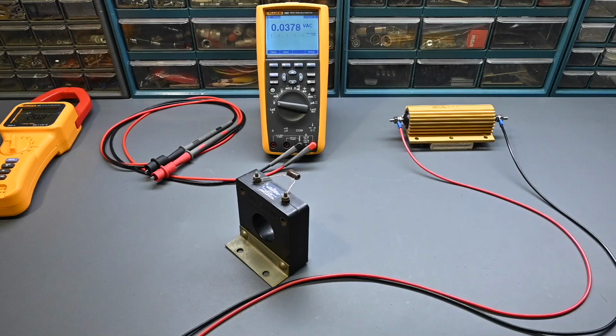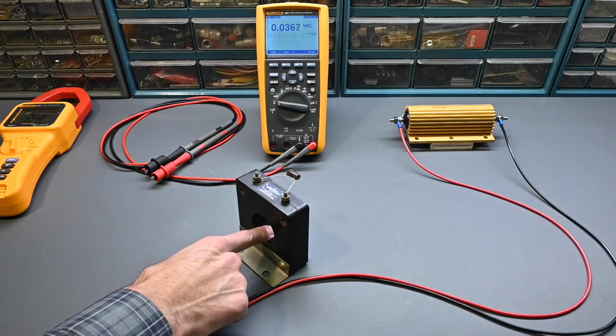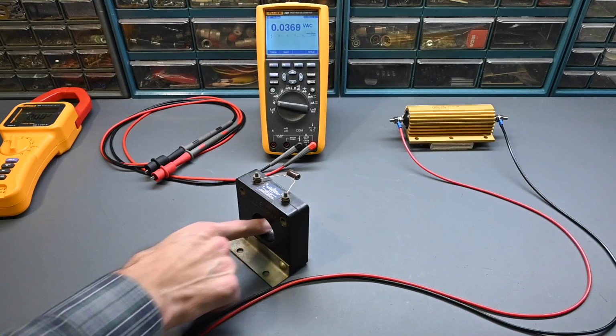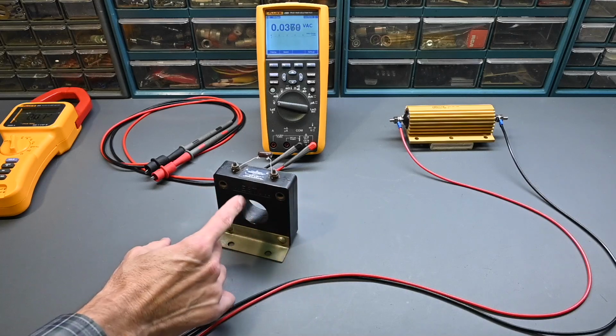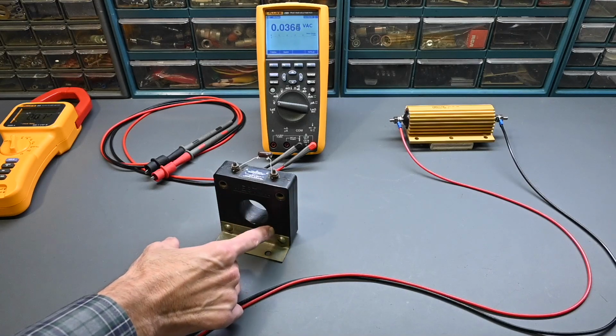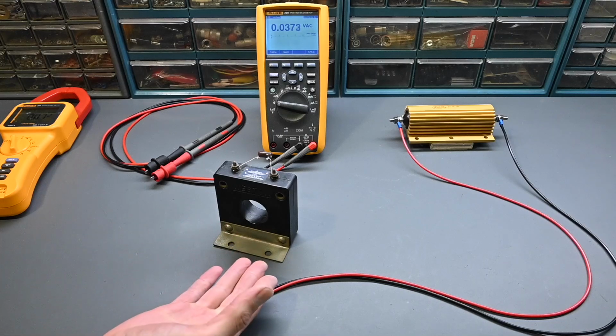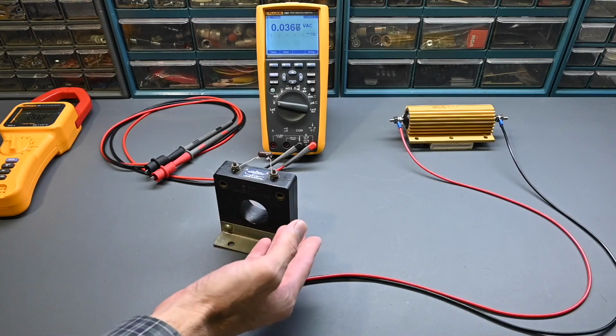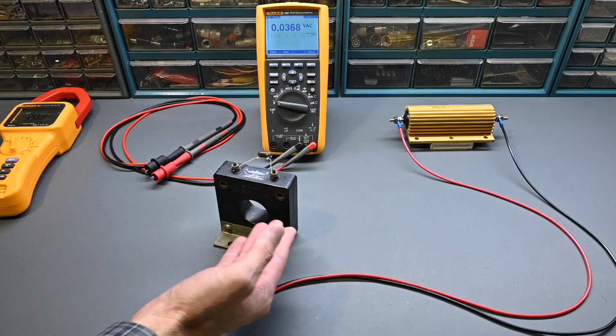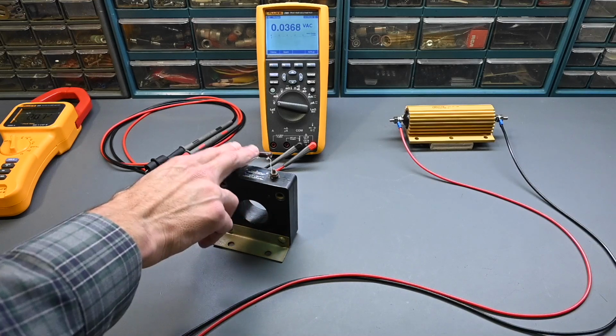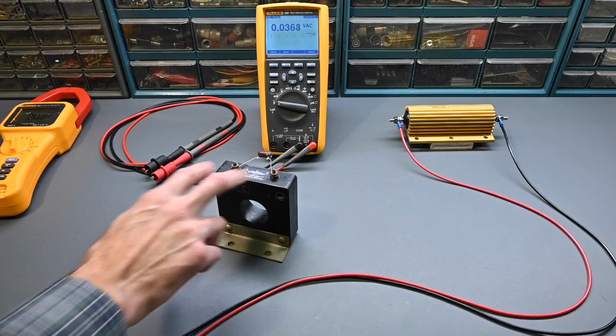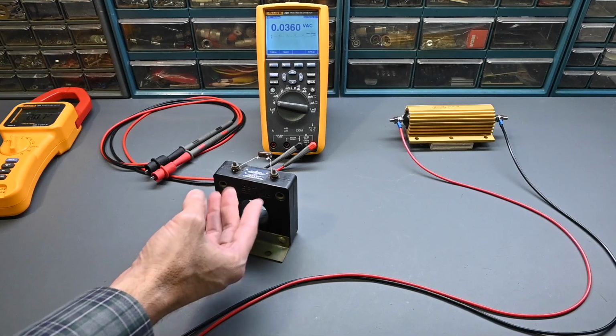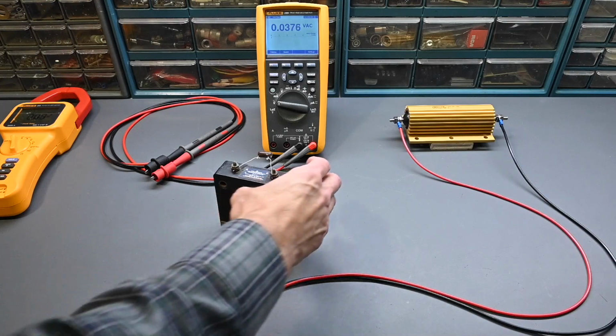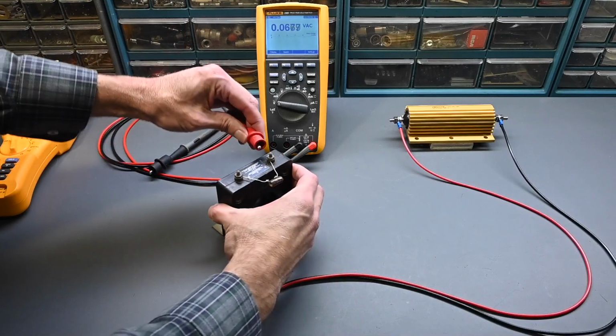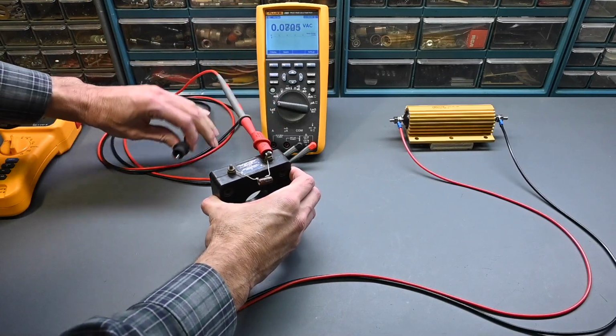But let's think about what's actually happening. So the wire that you're passing through the window of the transformer is the primary. So you could think of that as one turn. But in this transformer, there's a toroid in here, and it has hundreds of turns of wire typically, and basically gives you a step-up transformer of 1 to say 500 or 1 to 300 or something. It's a very, very high ratio. So if this isn't loaded by this resistor, you'll get extremely high voltage on these terminals, and it basically will just arc through the insulation on the windings. So let me take my meter, and I'm just going to move this over like so and connect to these terminals here.